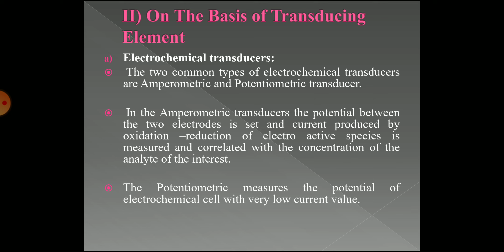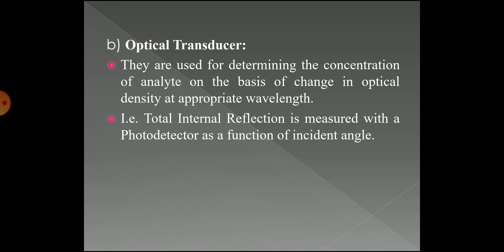Second one is optical transducer. They are used for determining the concentration of analyte on the basis of change in optical density at appropriate wavelength. That is, total internal reflection is measured with a photodetector as a function of incident angle.